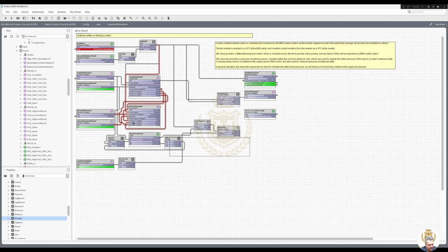I think that's the only way I'm going to. So I'm just going to tidy up this bit here. No, I'll leave it as it is. So extract fan flow. I certainly can't just put that enable to that, because just because we're enabled it doesn't mean there's flow. And the speed, well, we could do it. No, I can't do it from that because that's me sending a speed to it. I have got to do it from that sensor. And I'm going to have to know what the static pressure is first, so that I know that that sensor's working, so I know the fan's working.